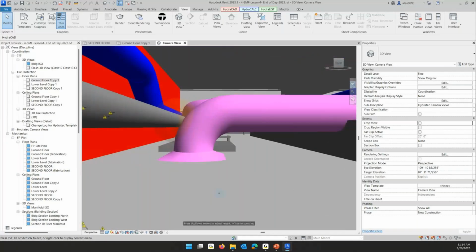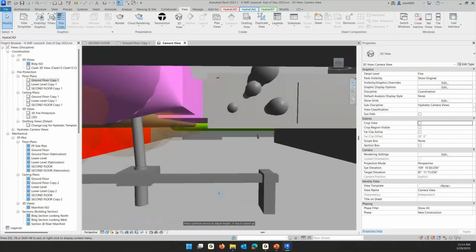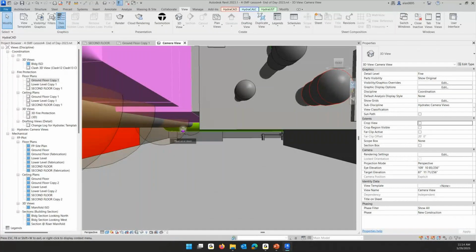And there's more investigation we could or maybe should do, but I'm going to say, generally speaking, I'm seeing a place I could sneak into this gap. This is a usual gap in sprinkler design. The lights take up the first 5 or 6 inches of the ceiling space, the space above the ceiling, and the other guys generally avoid that space. So if we moved down, the ceiling's at 9 feet. If we went down to 9'5" or 9'6", we'd maybe be missing a lot of that stuff.